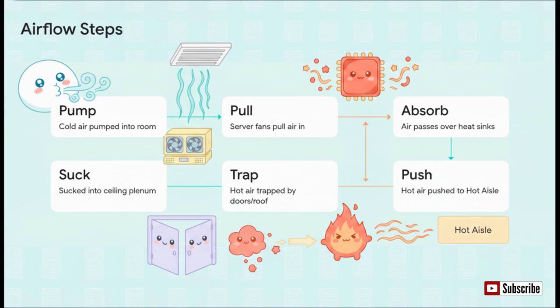Step 5, and here's the magic: that hot air is physically trapped. We're talking doors on the ends of the aisle and a solid roof on top. And finally, step 6, since it's trapped, it has nowhere to go but straight up, where it's sucked into the ceiling return plenum and routed right back to the chilling units. Pumped, pulled, pushed, trapped, and sucked.